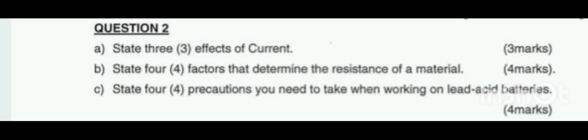Okay, are we together? Then the other one: do not charge the battery at a temperature above 49 degrees Celsius. Then the other one, you are supposed to avoid storing the batteries in a low charged condition. Do not store batteries in a low charged condition.